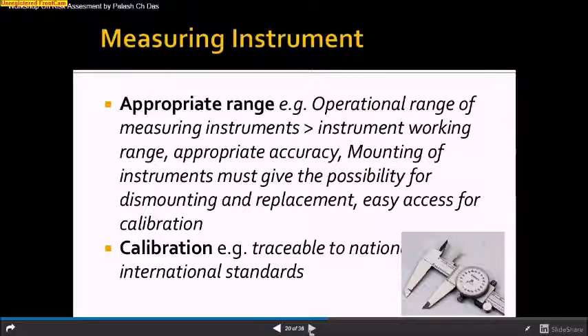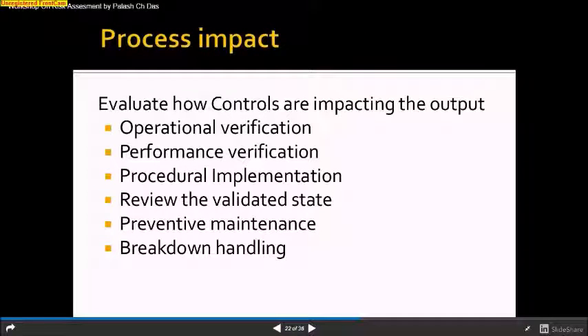When we discuss documents, we can say the component certificates, for whatever components are in the machines. The operational manual is also important. Machine maintenance manual, then SOP for cleaning and operations, training for the relevant staff, and preventive maintenance are also important portions. Once you have good maintenance practice for your machines, they will work for you long. Then, there is process impact. Process impact needs to be reviewed in terms of operational verification, performance verification, procedural implementation, and review of validation state, whether the machine is in the validation state or not, preventive maintenance and breakdown handling. How you handle the breakdown, and you should assess why the breakdown is happening and what corrective actions can be taken to reduce frequent breakdowns.